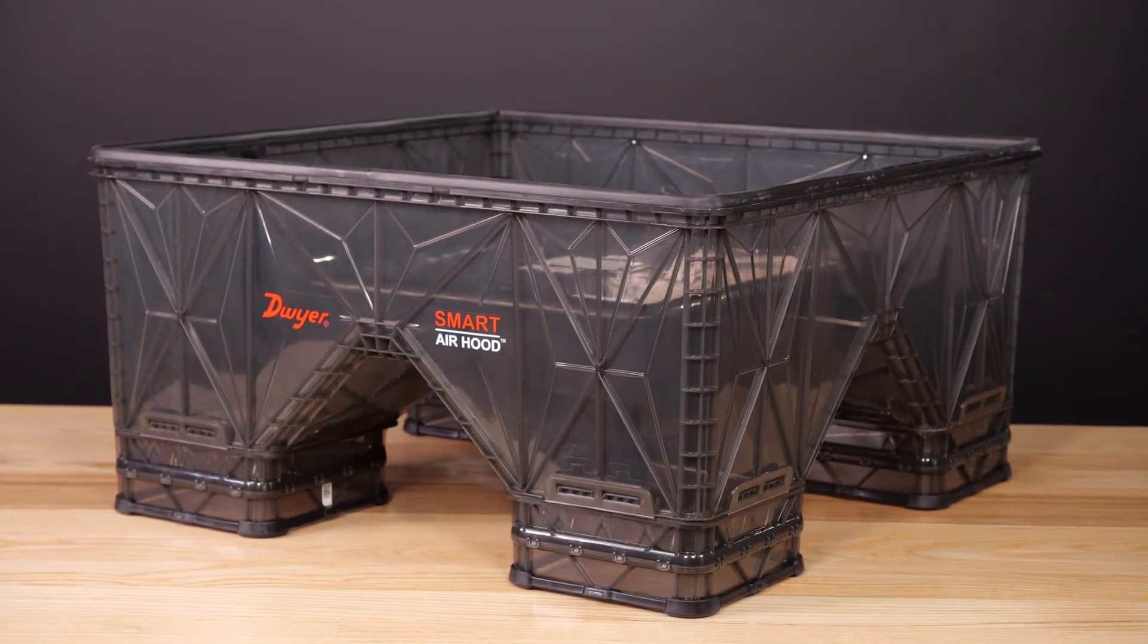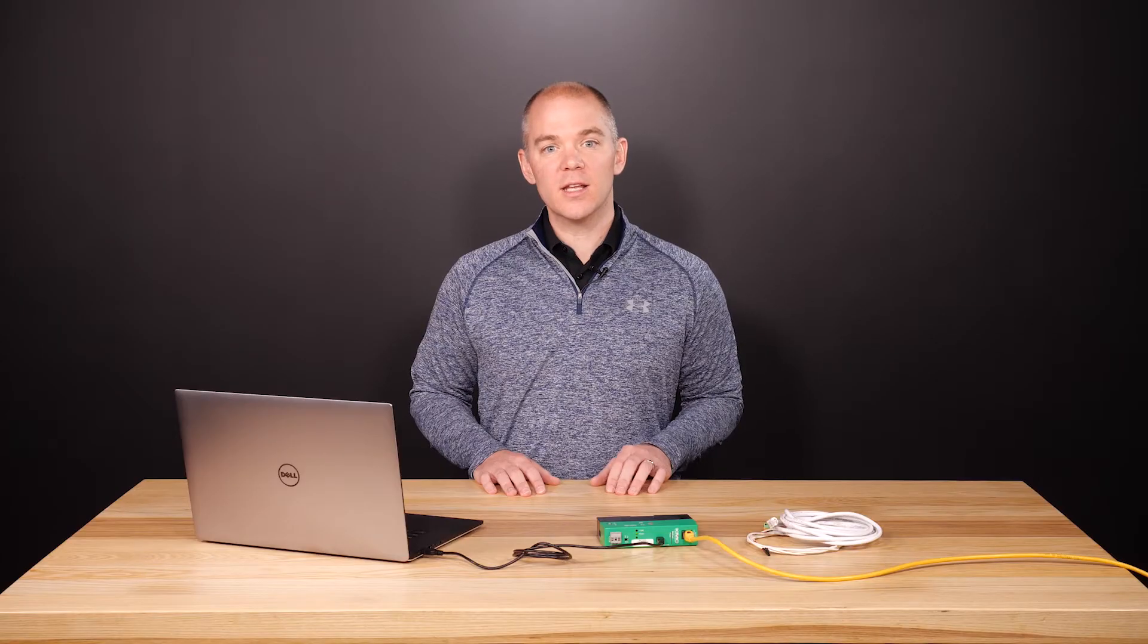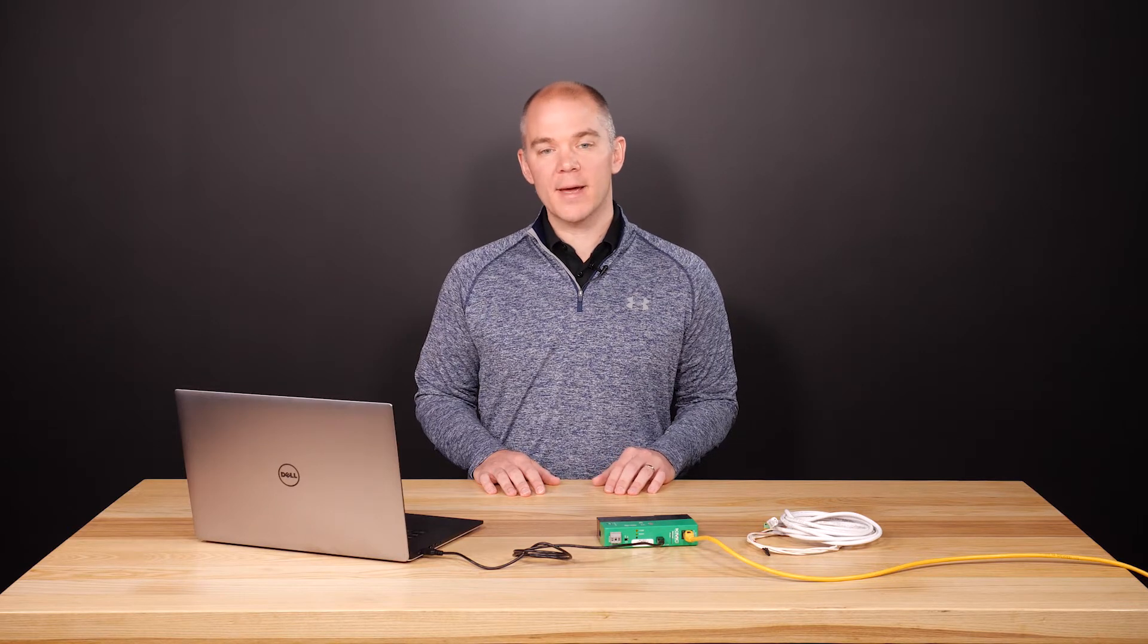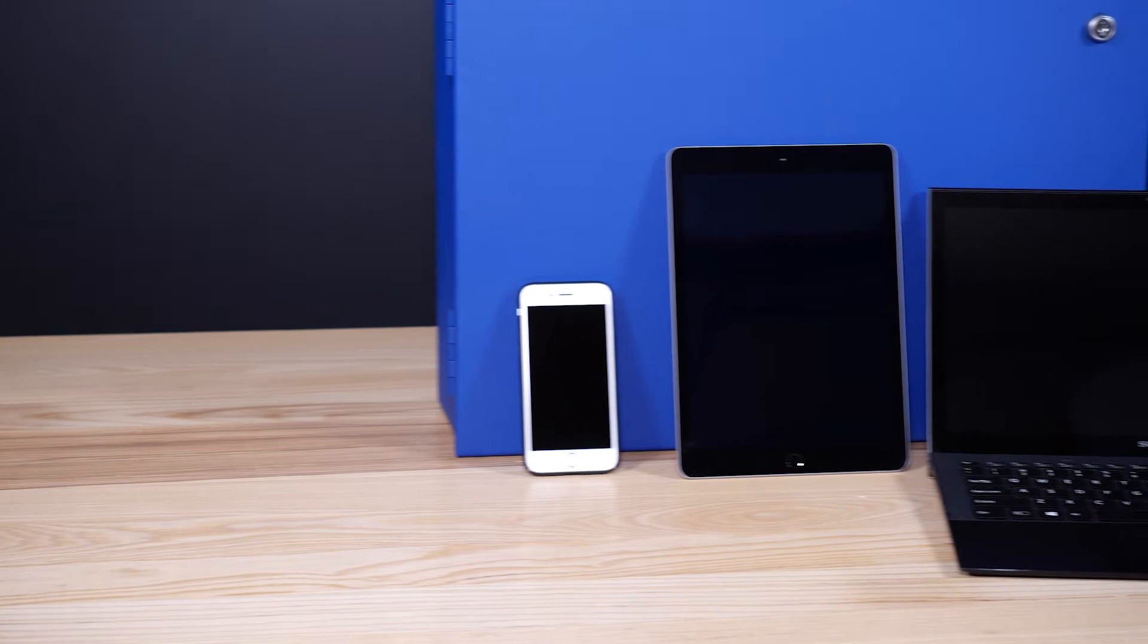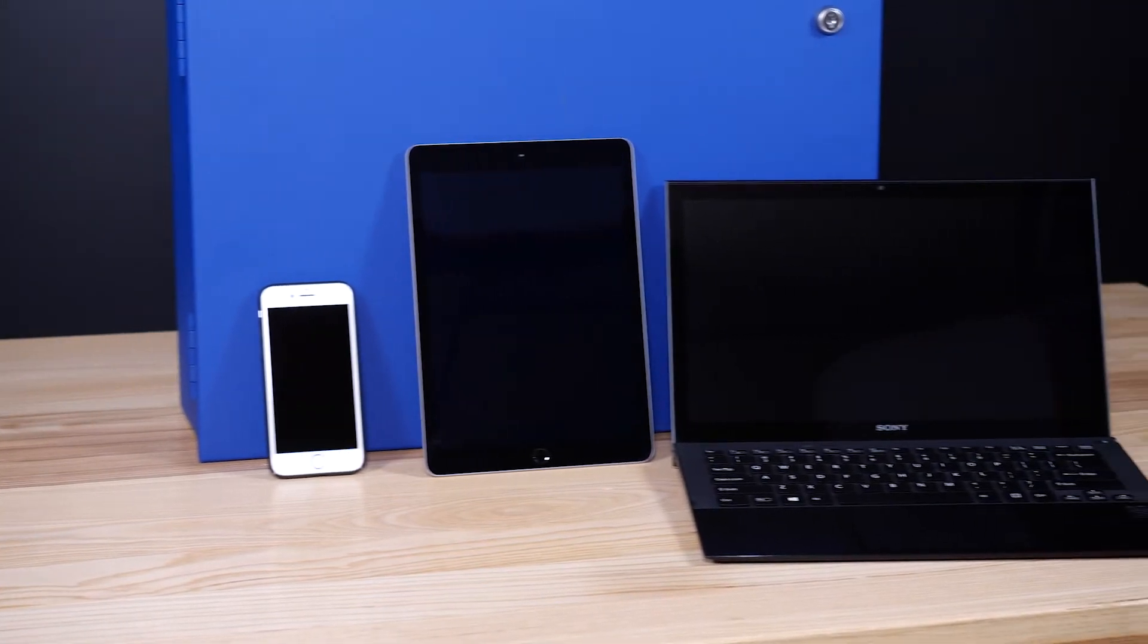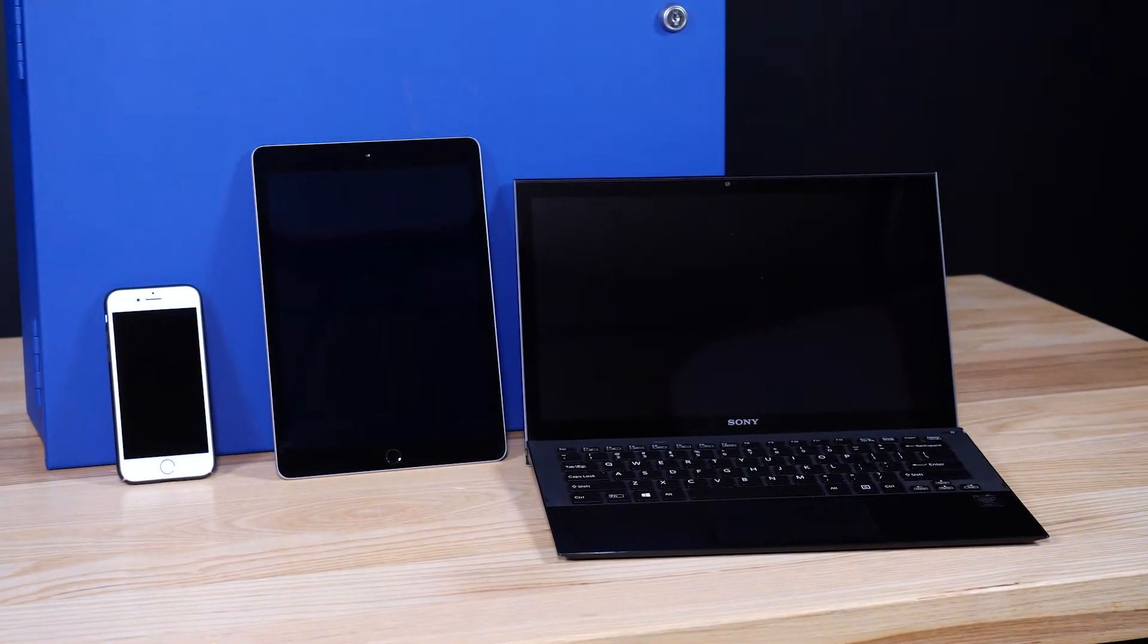First, a flow hood or other accurate method to measure airflow. Second, the engineering design specs for minimum and maximum airflow set points. Third, a device to access the router, such as a tablet, laptop, or smartphone. And fourth, a username and password with permission to the VAV balancing feature in the router.